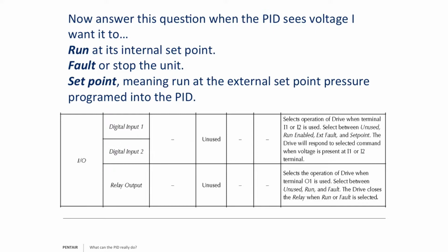So a lot of times when you're planning these, first of all, I find my drawing, or I draw out the circuit as I see how I want it to work. As we saw on the previous page, we're using the 24 volt onboard power supply, and we're using, I said, a float switch. Then I have to ask myself, when it sees voltage, what do I intend it to do? Run, like we just discussed? Maybe it's a fault. Maybe it's a water sensor, that when the water sensor gets wet, it sends a signal to stop the pump. Maybe it's a flow sensor, that when it sees demand going to, say, a different zone, when it trips zone 3, oh, that's a drip zone. Let's lower the pressure down from 60 down to 20 psi. So what do I want the drive to do when it sees voltage? And you have the 3 basic choices there.